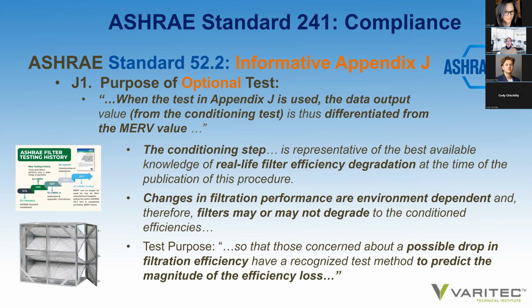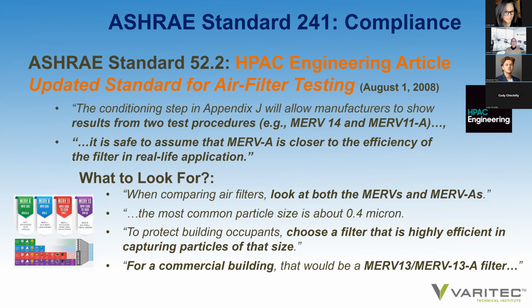The appendix goes on to say that when the test in Appendix J is used, the data output value is thus differentiated from the MERV value. And it is done because it creates a condition at the filter that is more likely to be present throughout a filter's operating life in a real application. So be aware of that, because the purpose of Appendix J was to address the concern of efficiency, a filtration efficiency drop during the operating use of a filter.